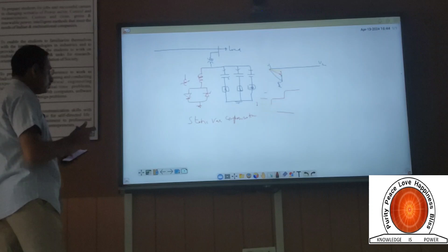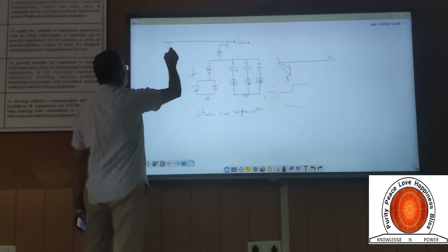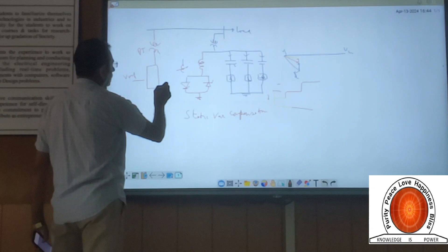That's why it is called the VAR compensation. And on what factor will the firing angle of the thyristor depend? Suppose with the help of the potential transformer, we measure the voltage here, and this measured voltage is compared with the reference voltage. If it is 1 per unit, then there is no need to change the firing angle. From here, there will be the firing angle change. From here, the firing angle of the thyristor will be set.